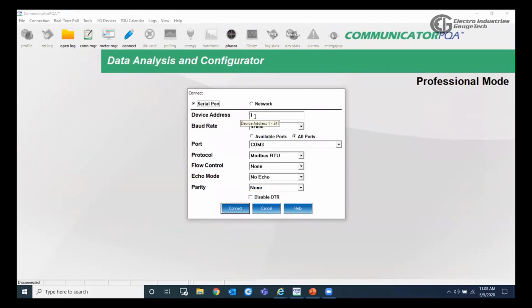So the device address can be a number between 1 and 247. By default, the device address would be 1 for all the communication ports. Then we have the baud rate, which can be any of these baud rates, and again, the default is 57600. Then we have this option where we can hit available ports. The available ports will give you what's connected to your USB, to your laptop. As you can see here, it's telling me that I have a USB serial cable connected to port COM3.